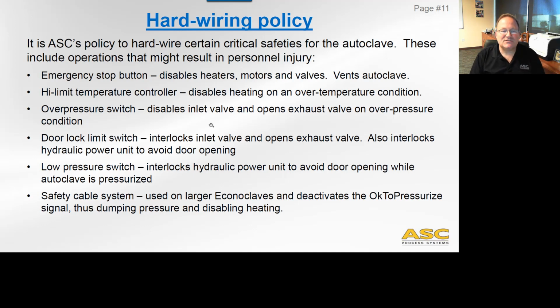Okay. Now, interestingly, if you happen to be at elevated temperature and you hit the e-stop, it's going to shut off all the pumps, all the cooling pumps too, so it will remain at that elevated temperature because the e-stop condition is not going to allow pumps to operate because that's a powered device. High limit temperature controller, that's an individual independent controller which monitors a thermocouple and will provide a latching signal to the PLC and to the relays that will indicate an over-temperature condition.